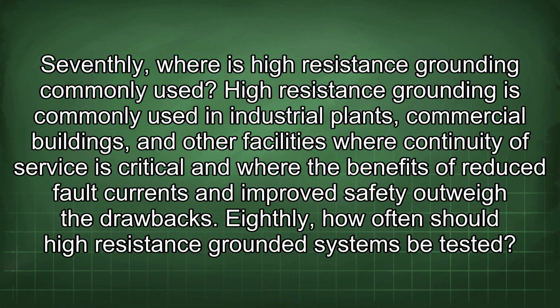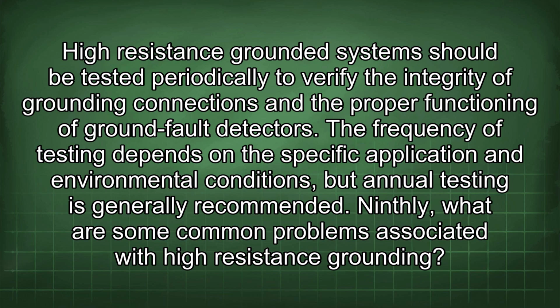Seventhly, where is high resistance grounding commonly used? High resistance grounding is commonly used in industrial plants, commercial buildings, and other facilities where continuity of service is critical and where the benefits of reduced fault currents and improved safety outweigh the drawbacks. Eighthly, how often should high resistance grounded systems be tested? High resistance grounded systems should be tested periodically to verify the integrity of grounding connections and the proper functioning of ground fault detectors. The frequency of testing depends on the specific application and environmental conditions, but annual testing is generally recommended.